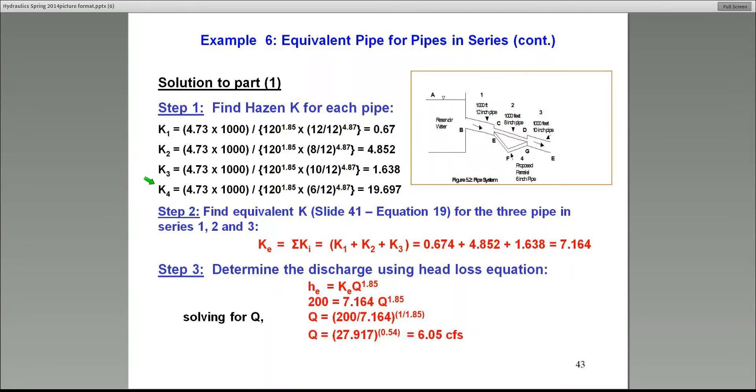For pipes 1, 2, and 3, they're all in series. So the equivalent pipe is the sum of all the Ks: K1, K2, and K3. It gives me an equivalent K of 7.164.